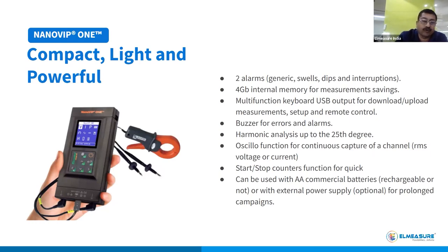For example, say this is connected to a motor and you want to monitor it for at least 2-3 or 4 hours. You connect it and leave it. You can set it to record 1 second data or choose any other option provided in this meter, and monitor things like energy, kilowatts, and power factor with respect to kilowatts.